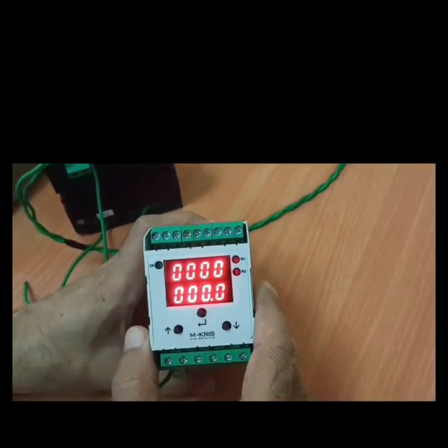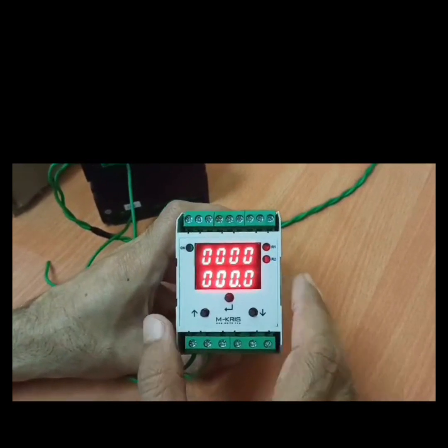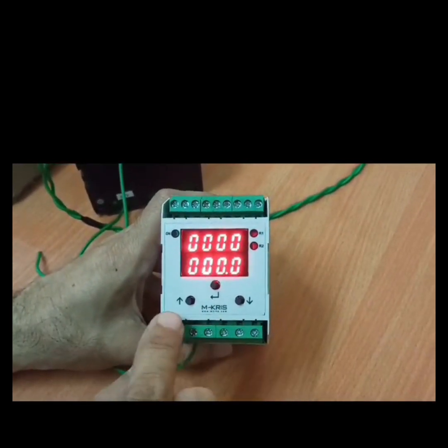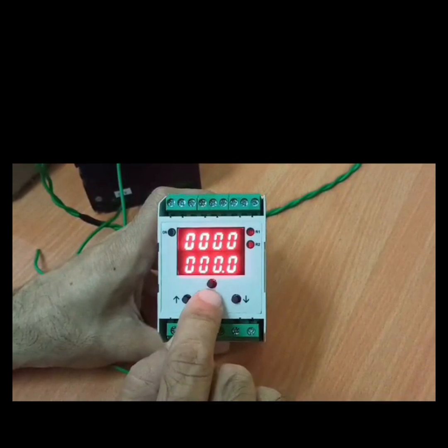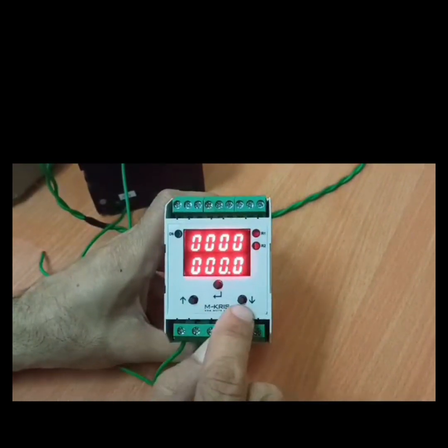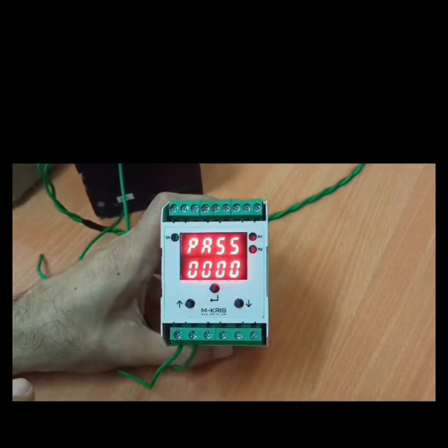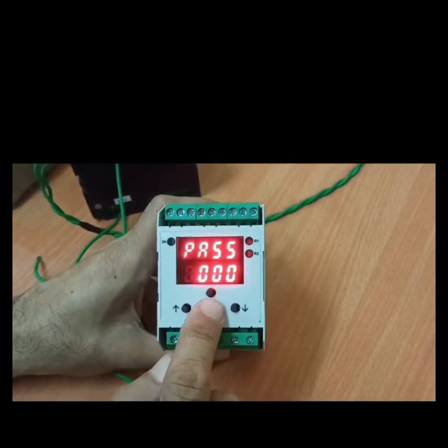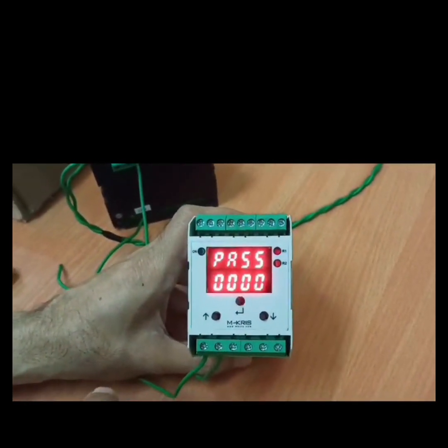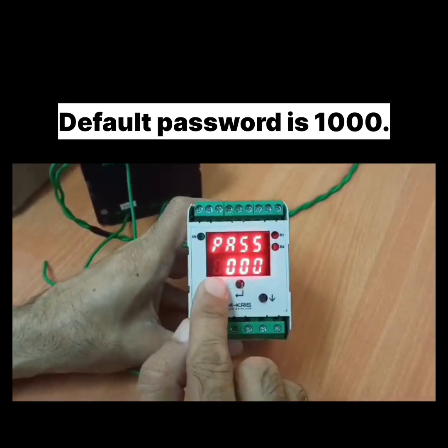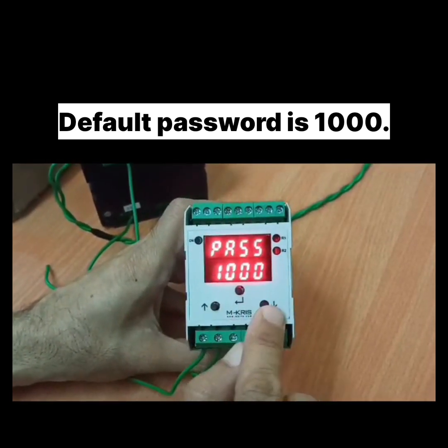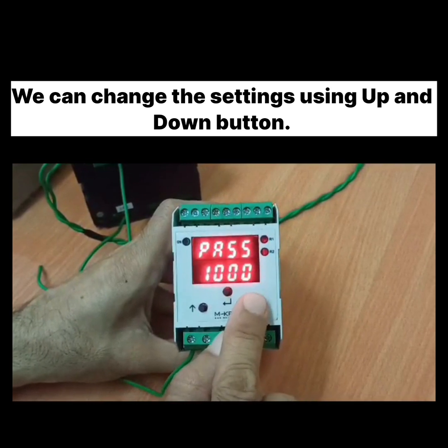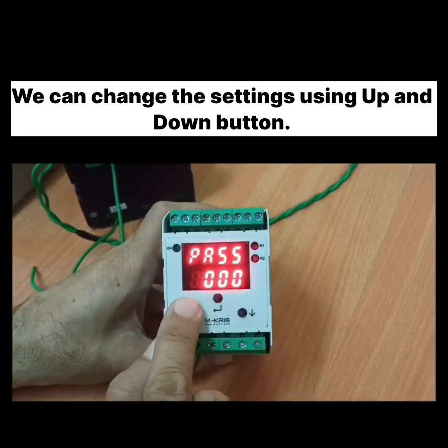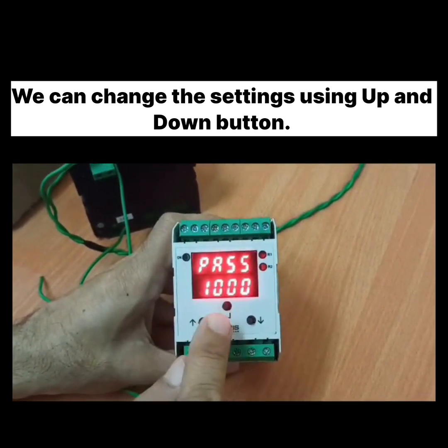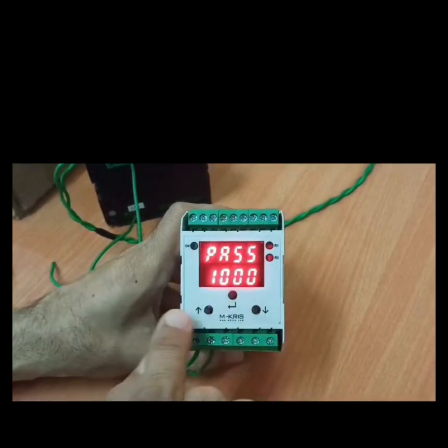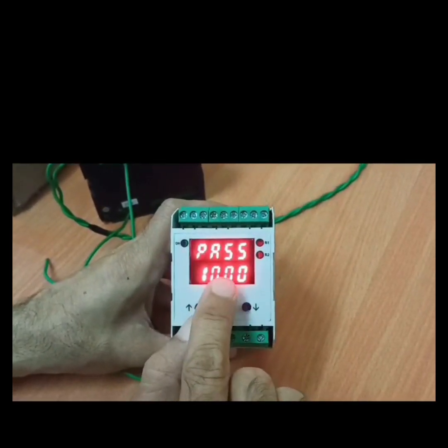Now let us look at what settings you need to make in order to make it functional. For settings, we need to have a look at the switches. This is the menu switch in the center, and up and down. By pressing the center menu button, we can access the password page. The default password is 1000. Using up and down, we can change the settings, like this can reduce and this will increase. We can move to the next digit by pressing the menu button.